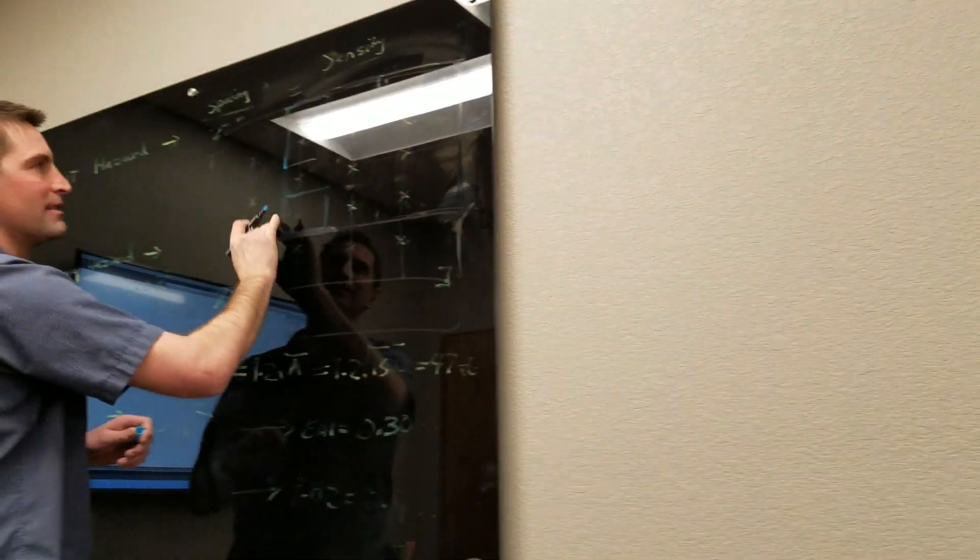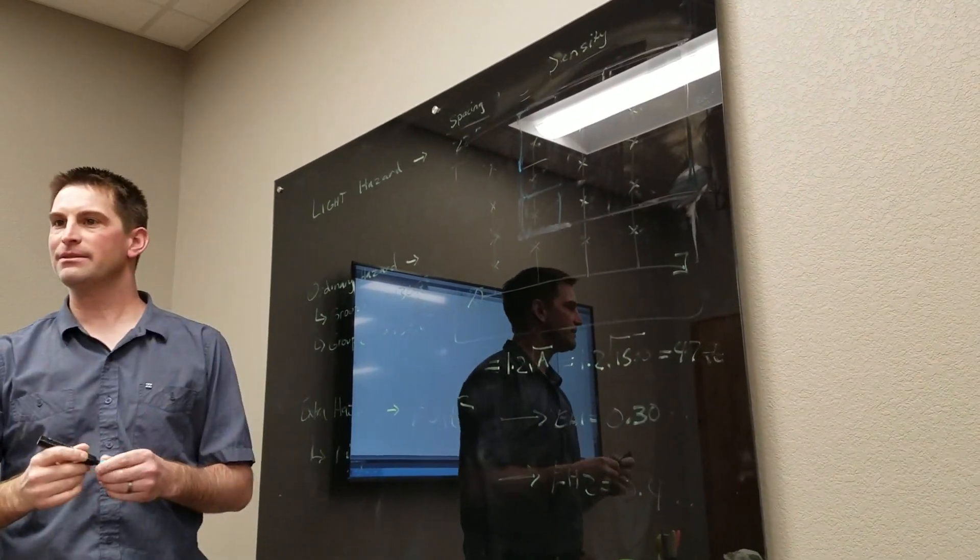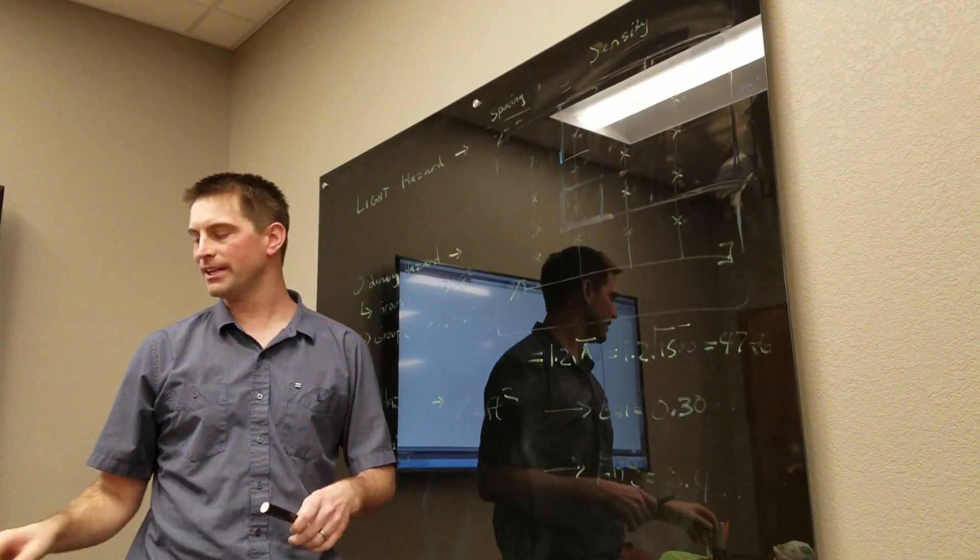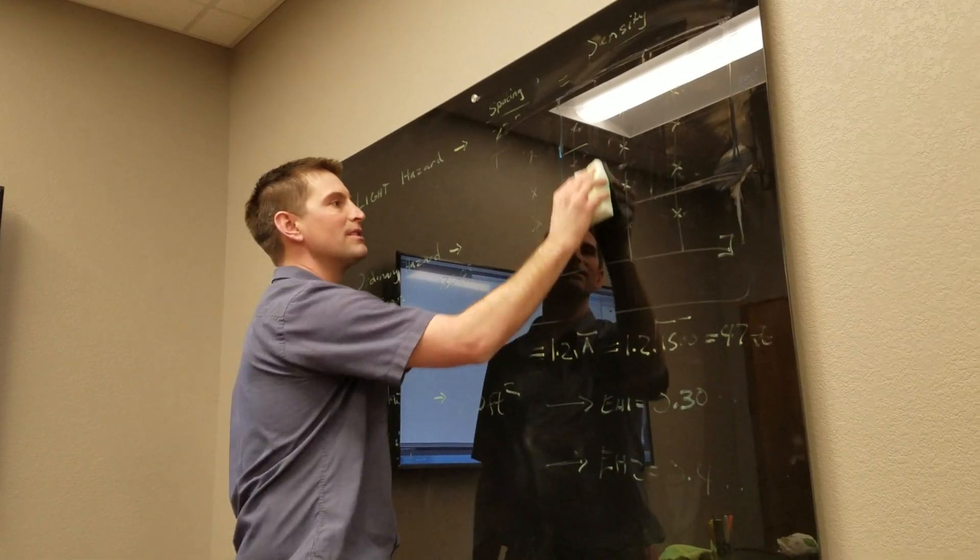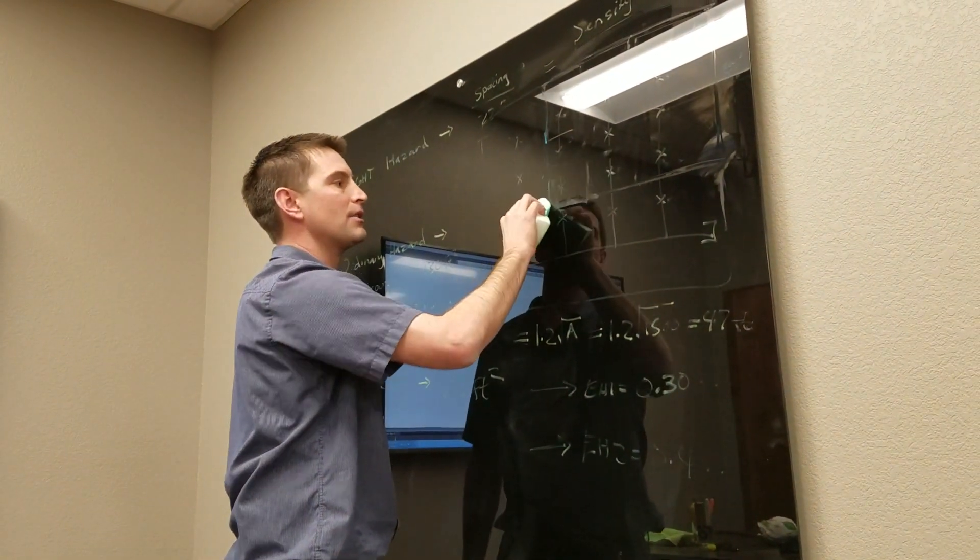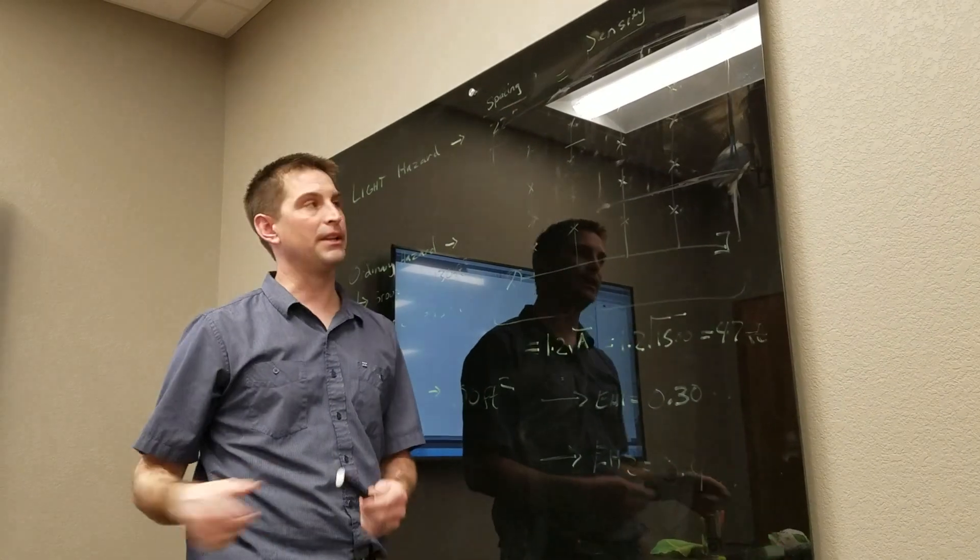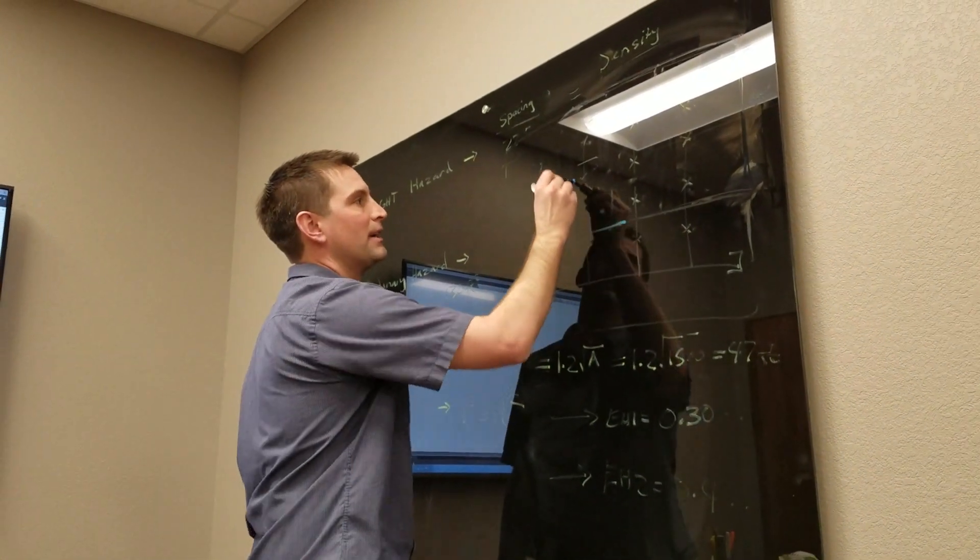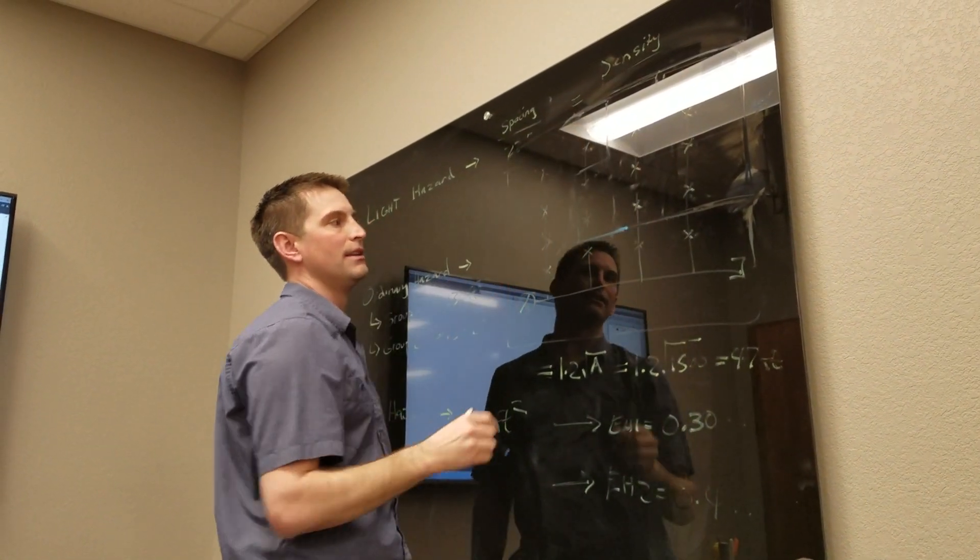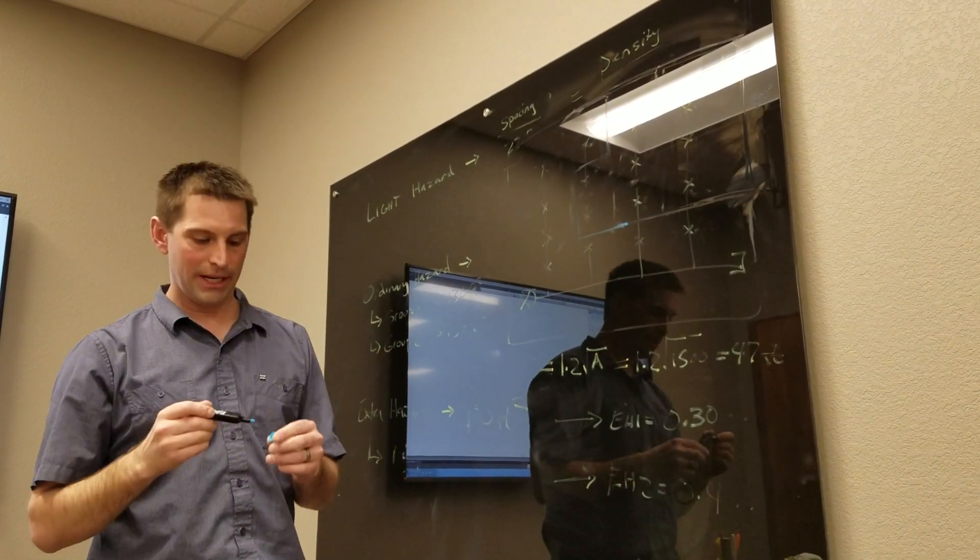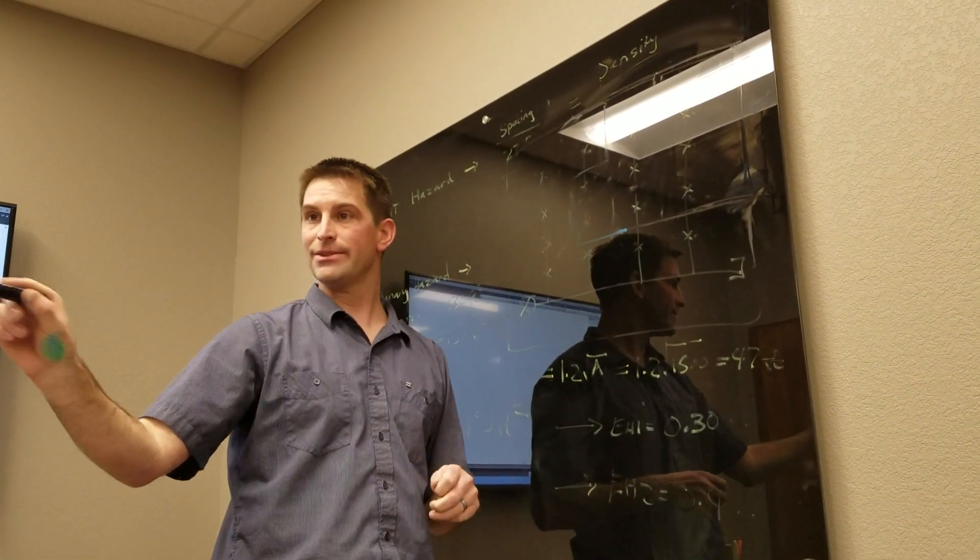But the closer ones do have more water. That's what your head tells you. That's what everybody gets confused about. The code is actually the way they tell you to do it is correct because it will be more demanding. I promise you, if you run the calculation by picking up these and cutting out this head, it will be more demanding because of this fact.